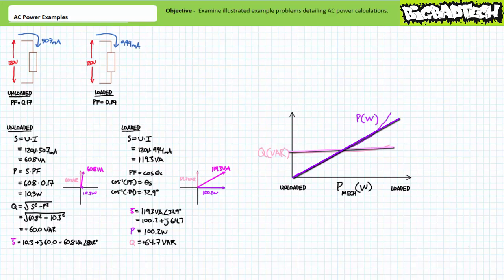Whereas real power consumption increases almost linearly. This implies that induction motors consume real power roughly linearly proportional to the applied load, but at all times must consume a relatively constant amount of reactive power simply to keep the motor spinning. We'll examine this feature and much more about induction motors in later lectures.